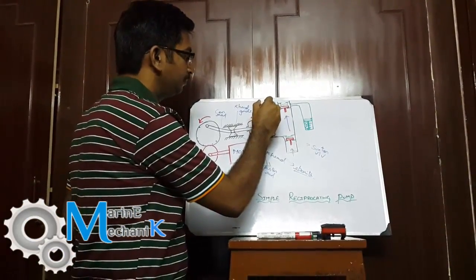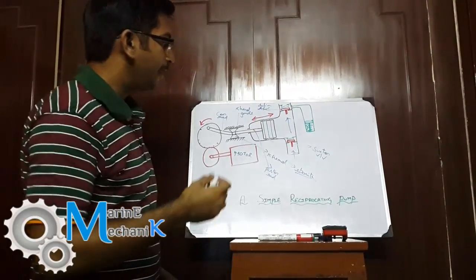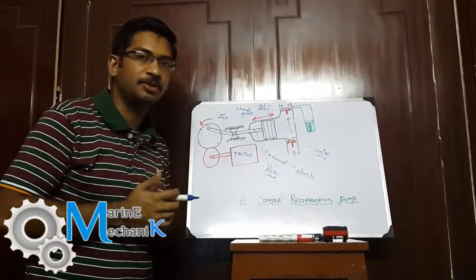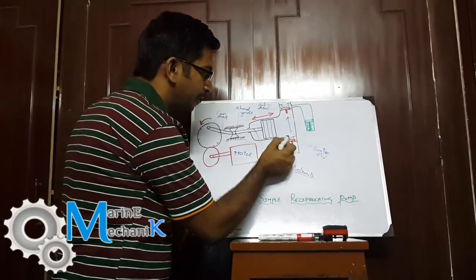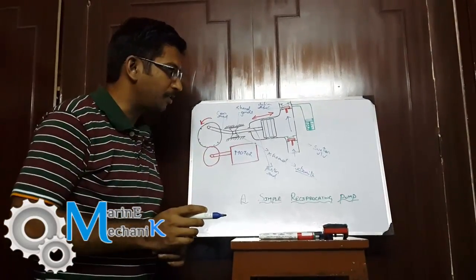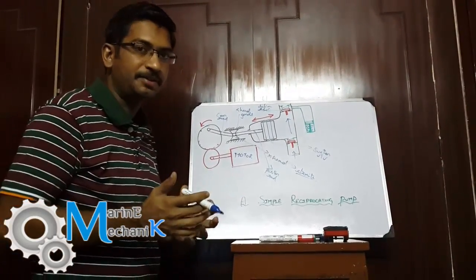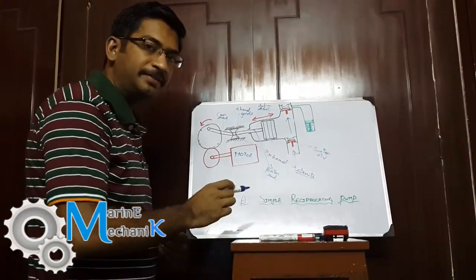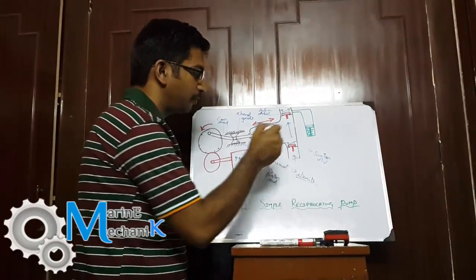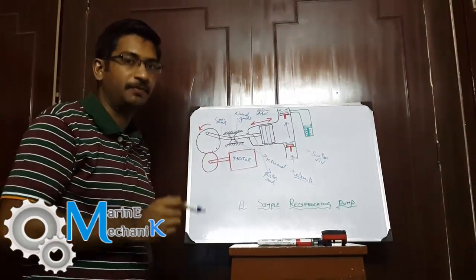One main failing point what the examiners look for is the springs over here. The Google pictures will show this, but on board ship, on the valve chest upon the suction valve and delivery valve, you will definitely have springs for positive closing of the valves.